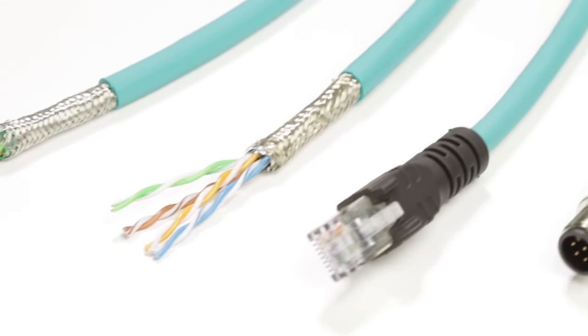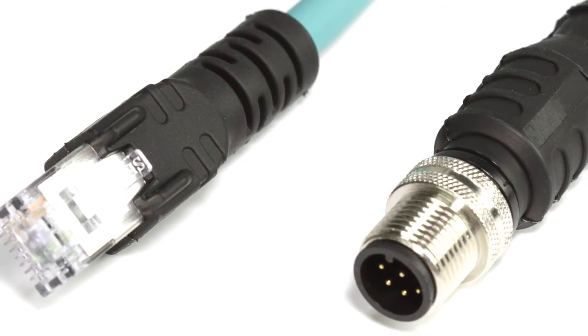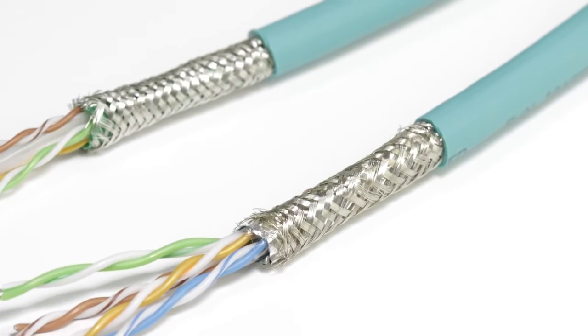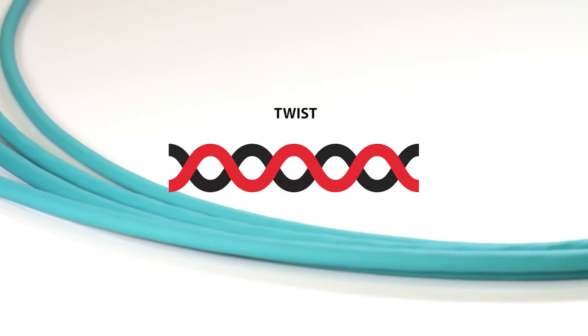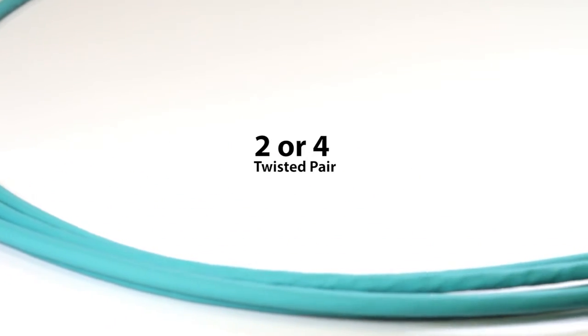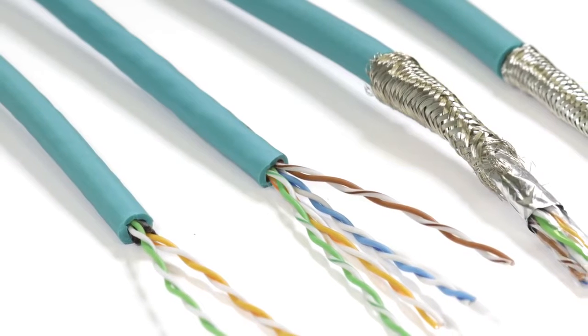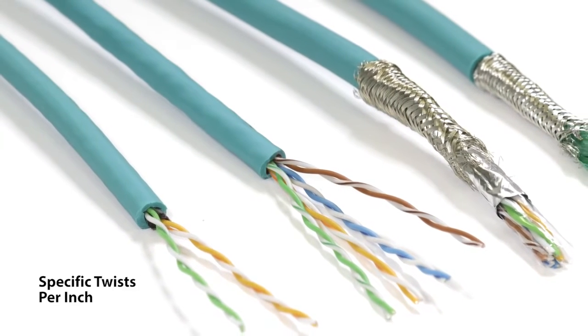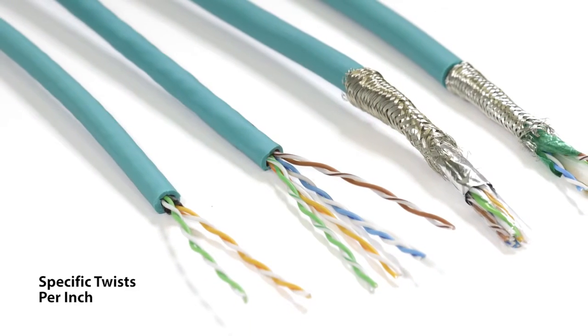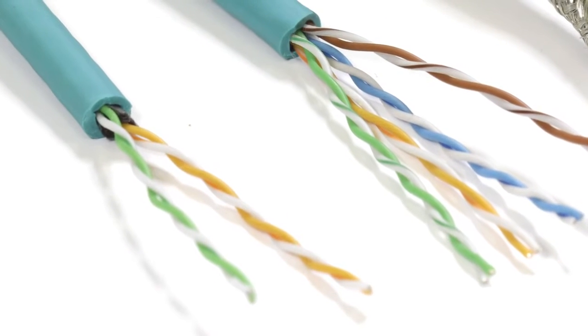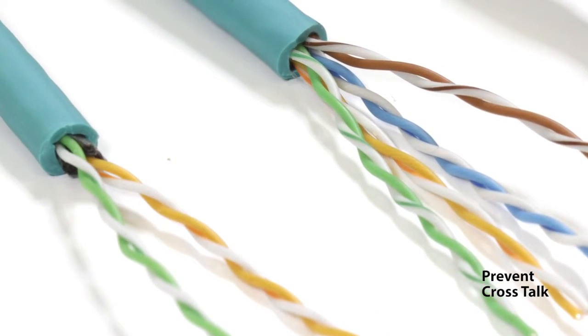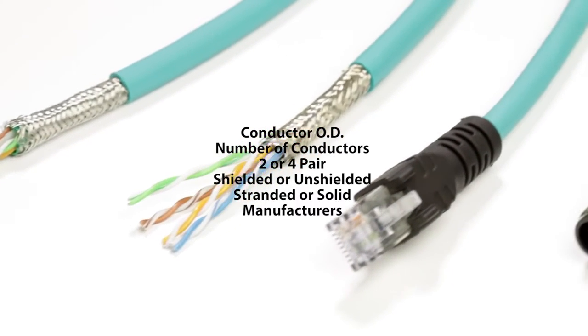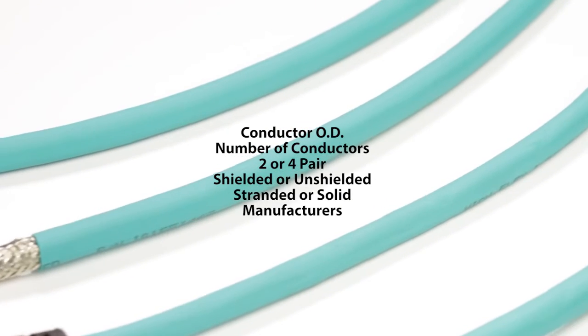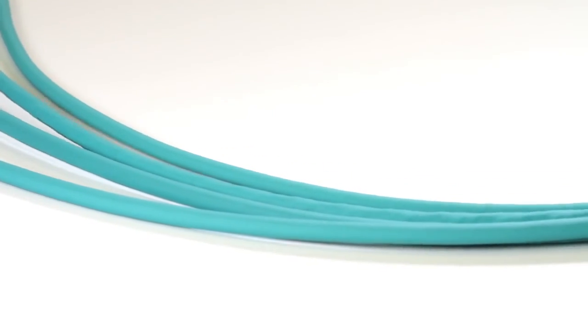From a cable perspective, different construction methods are needed to meet the speed requirements of each category, and it's all about the twists. Ethernet cabling consists of either 2 or 4 twisted pairs. Each cable construction is designed with specific twists per inch for each individual pair. Each pair needs to be different from other pairs in the cable to prevent crosstalk, especially between unshielded twisted pairs. This will vary by conductor OD, number of conductors, 2 or 4 pair, shielded or unshielded pairs, stranded or solid conductors, and also differs between manufacturers.